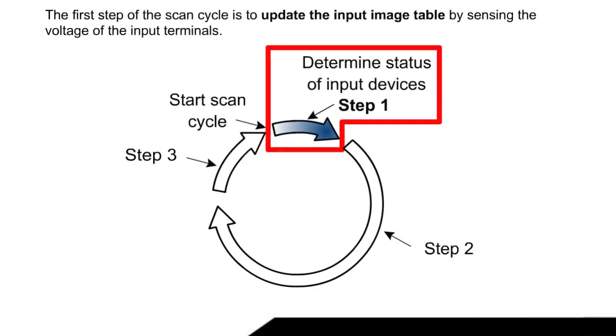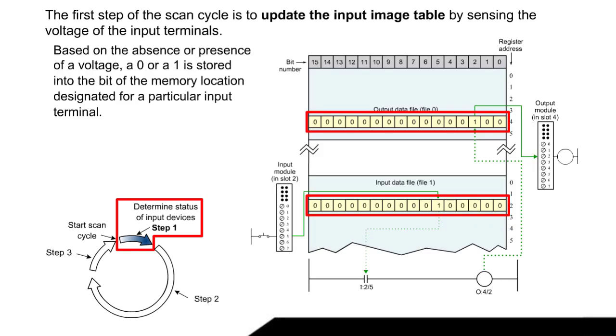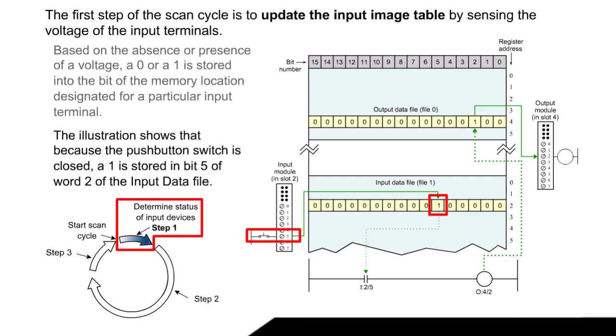The first step of the Scan Cycle is to update the input image table by sensing the voltage of the input terminals. Based on the absence or presence of a voltage, a 0 or a 1 is stored into the bit of the memory location designated for a particular input terminal. The illustration shows that because the push-button switch is closed, a 1 is stored in bit 5 of word 2 of the input data file.